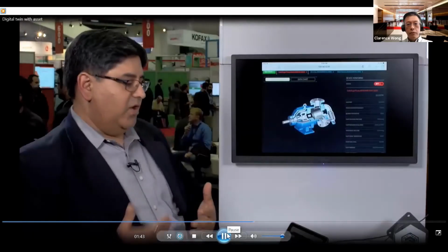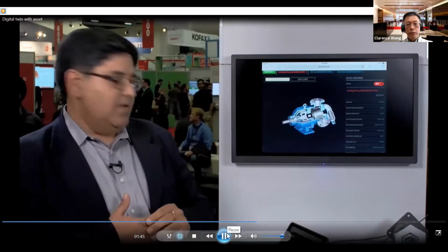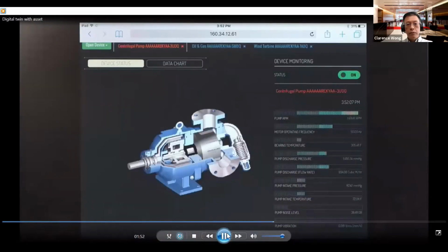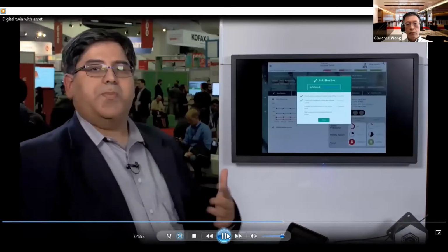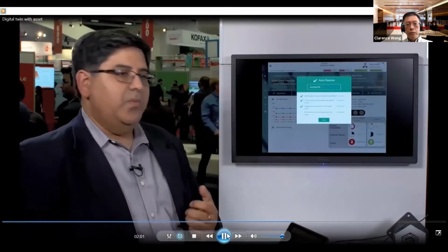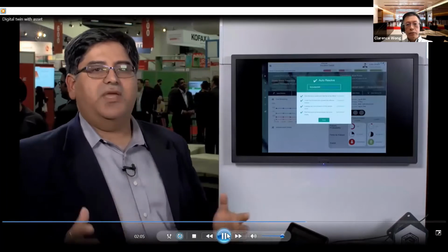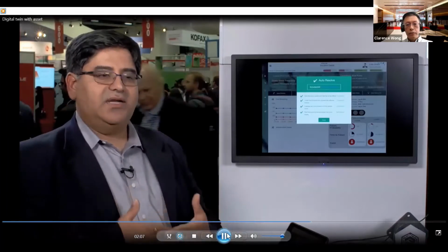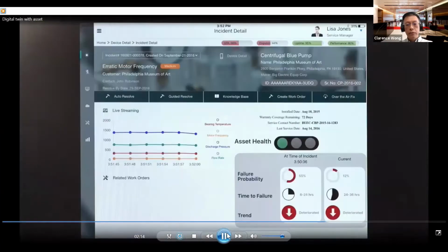What we will notice is the probability of failure dropping down from the 20-30% range to an acceptable range of 6%. Now, let me talk about the analytics and the probability of failure. That has been done using Oracle's Big Data Cloud product suite, where we have analyzed the raw data from hundreds of pumps over a period of time and arrived at the computational model that helps us determine if the pump is about to fail. While we were speaking, you can see that the probability of pump failure has gone down into the 6% range. And at the time of the incident, it was close to 55%.